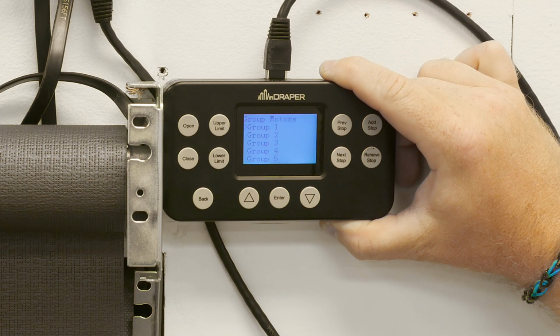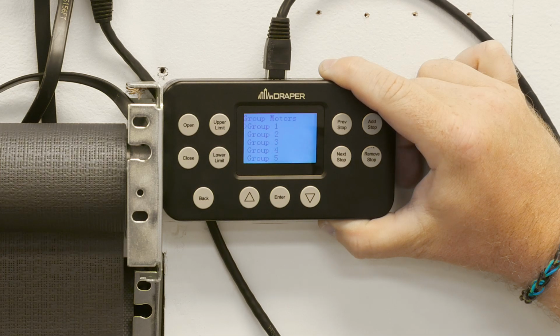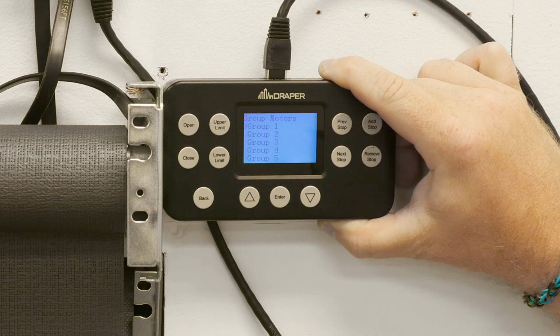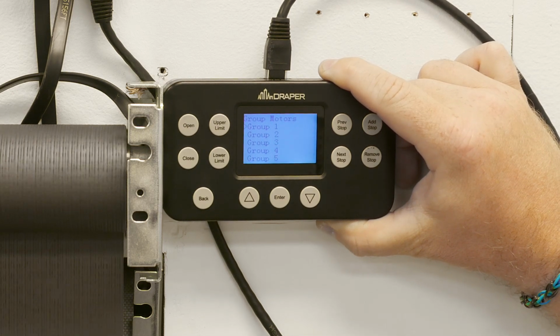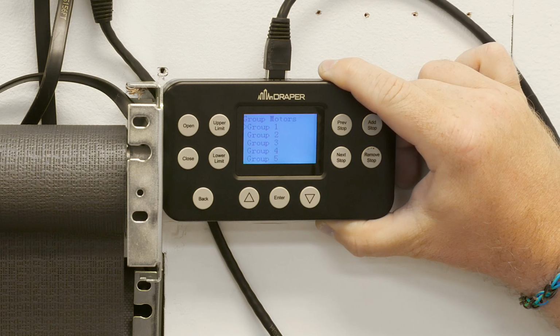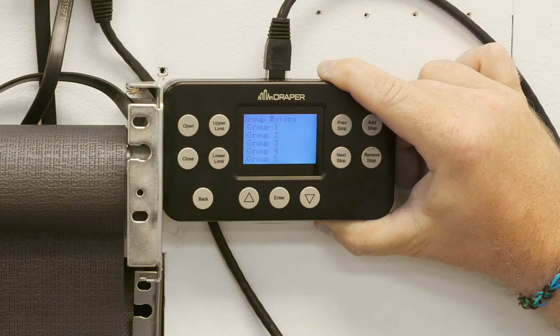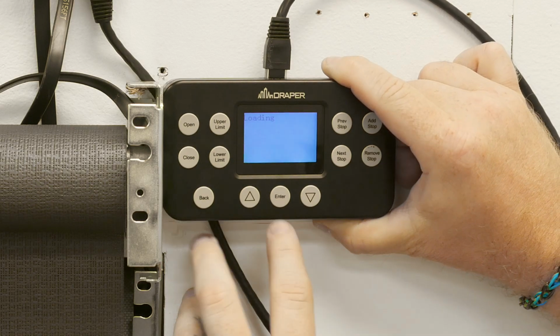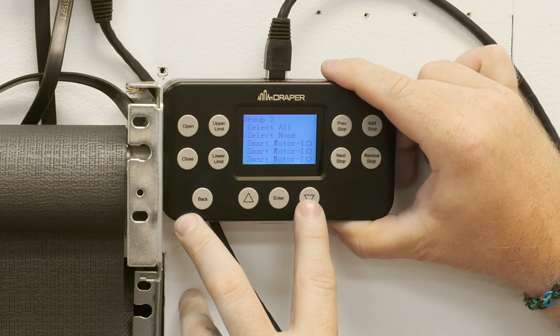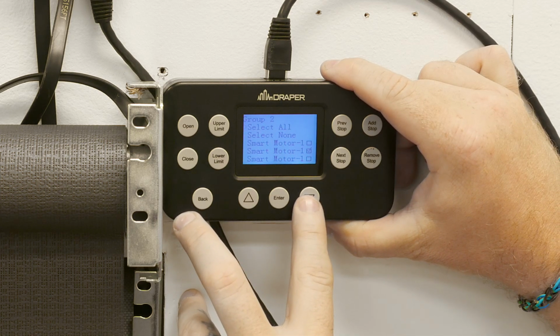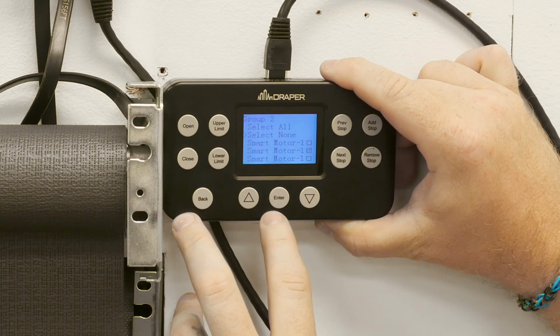To confirm that I have the correct motors in here, any shades that I have selected as part of this group are now going to jog up and down to say, hey, we are the group that you just created, are we correct? If yes, you can move on. If no, select the group and go in to modify it. My two motors are correct, so I'm going to move on. Now I'm going to go to group 2. Now I want to put my other two motors in this group, so I'm going to select this one and this one.